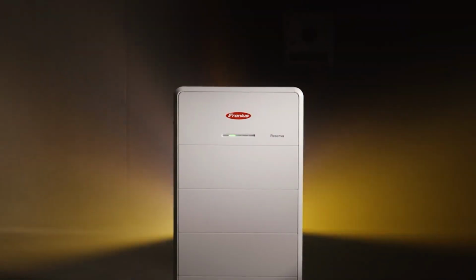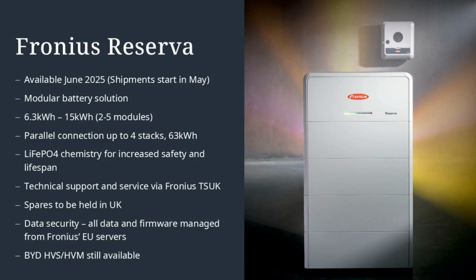Finally, another really important product that's coming from Fronius in the coming months is the Fronius Reserva battery. The Reserva is Fronius' own battery solution. It is designed specifically to work with the GEN24 and Plus inverters. It is a modular solution, and you can build it up between 2 and 5 battery modules, meaning that we can have stacks of 6.3 up to 15.8. We can then parallel stack up to 4 of these towers, meaning that we can have a maximum system capacity of 63 kilowatt hours. Of course, we're using lithium iron phosphate technology, which is the most stable, safe, secure, reliable battery technology on the market.